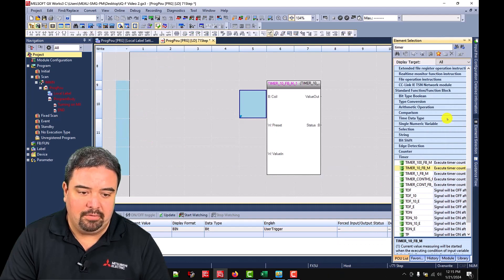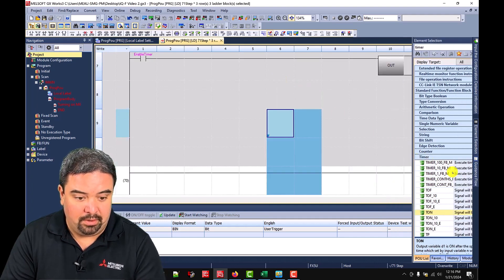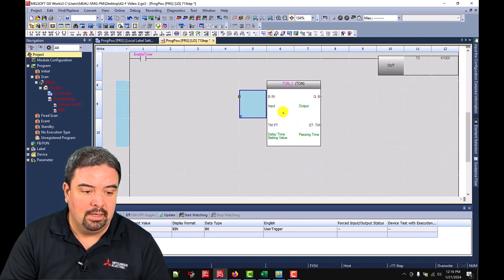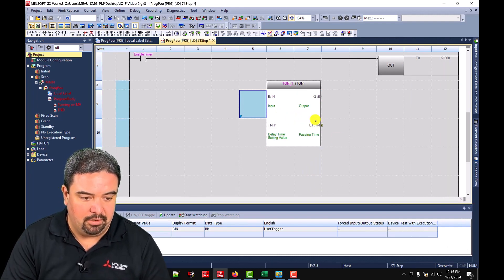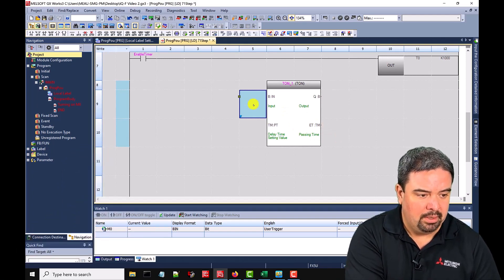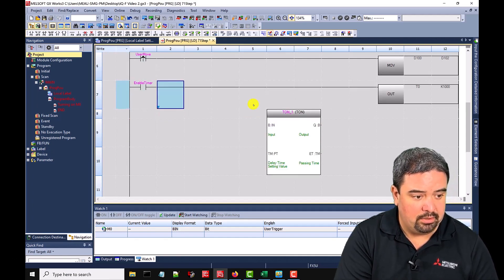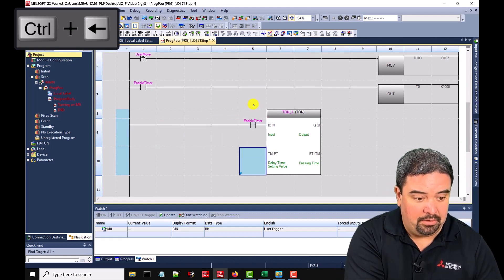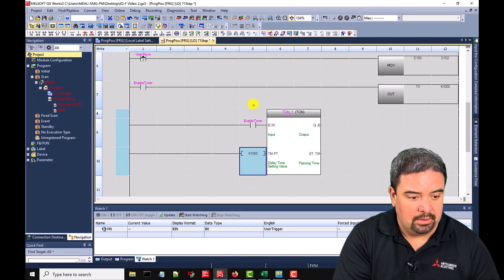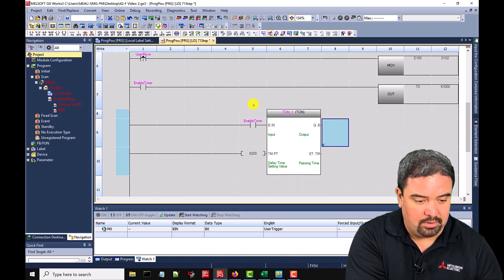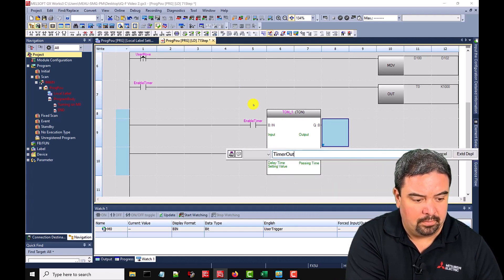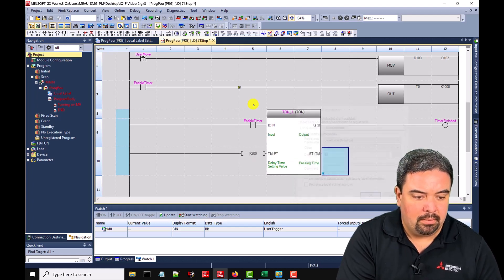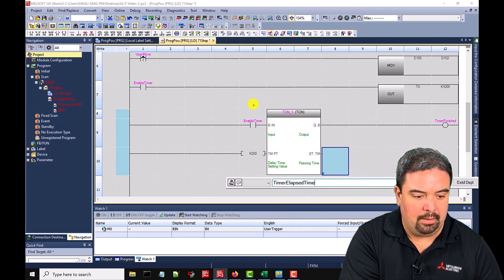We also have the TON instructions and TOF. So if you're more familiar with TONs and you want to use TON, we can bring that into the project. And then you'll see your B, your Q, your timer, and your ET, your past time. So I can go ahead and program this. We'll have an input. So why don't we use the same enable timer up here? So we'll copy that here and then I can hold down control and hit over, give a value to that. So K 1000. Actually, we'll just make a difference. We'll do K 200. And then here will be our output. So timer finished. And then the past time, so timer elapsed time.